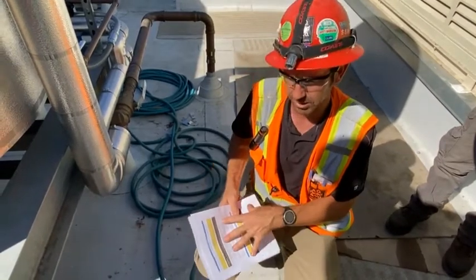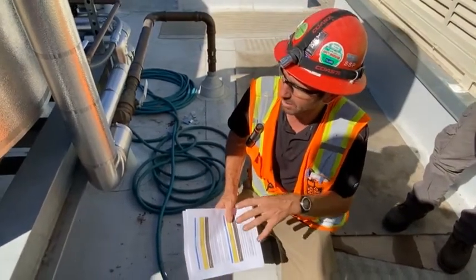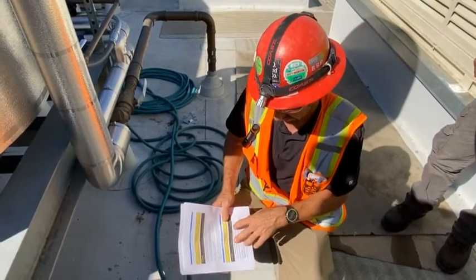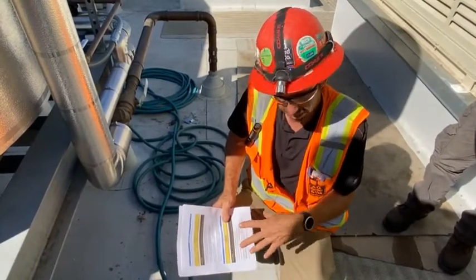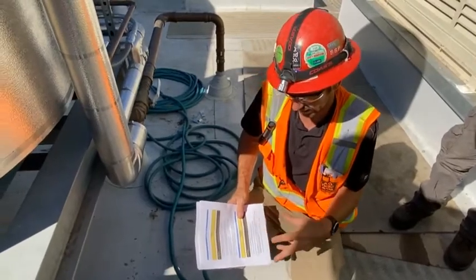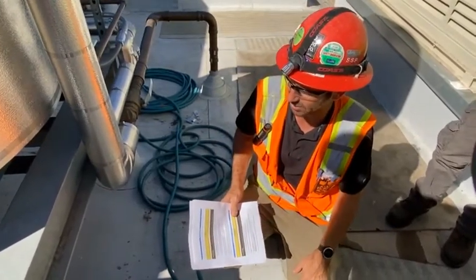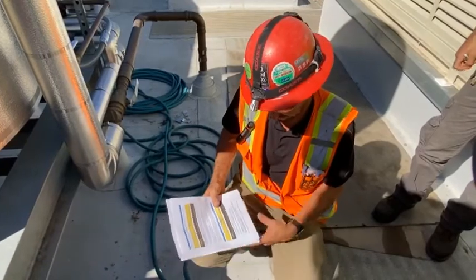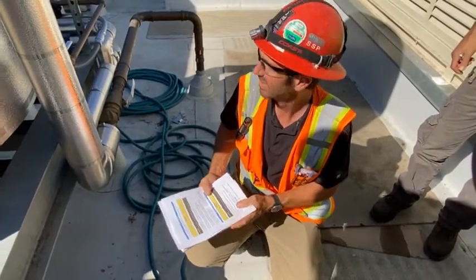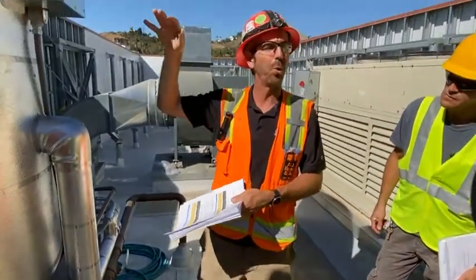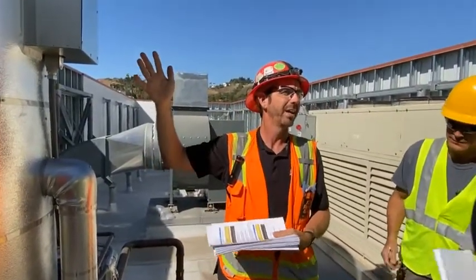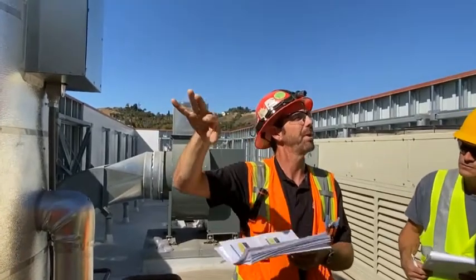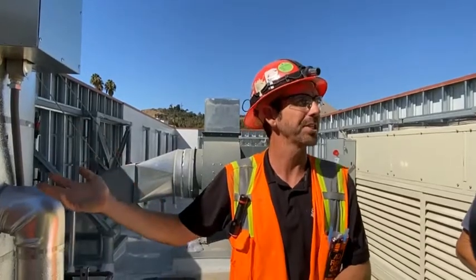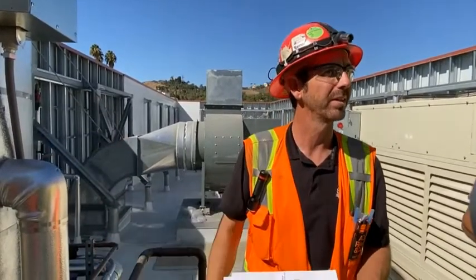Yeah, just check back in with the actual maintenance O&M for the type of cleaning procedure, but that cleaning of this tank right here will be an annual process. Obviously, when you're draining the tank, you're going to need to make sure you schedule that. There's no bypass around the tank to provide hot water for the building, okay? So know that when you're doing that inspection, you're not going to have hot water to the building, okay?